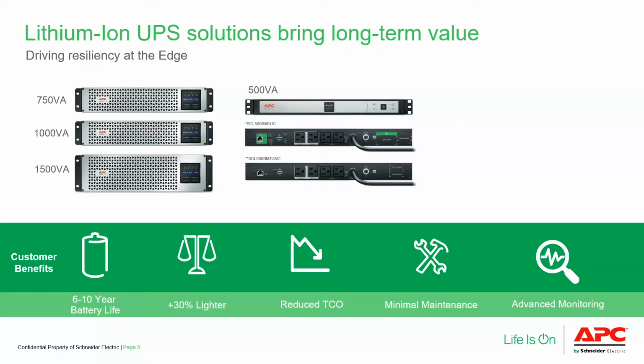For this product line, you're also looking at enhanced visibility. We can put a network management card in this unit, similar to our other UPSs, and connect it to EcoStructure software. We recommend using a network management card when you have 5 or more UPSs in your fleet. Below 5, we recommend using the RJ45 port built into the back of the UPS, which provides one-way communication to a complementary EcoStructure app. It gives basic health information—not as granular as the software—but enough to know when a battery has died, when a UPS is off, or if there's any other critical issue with your unit.